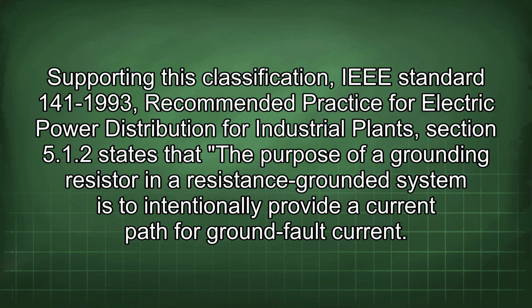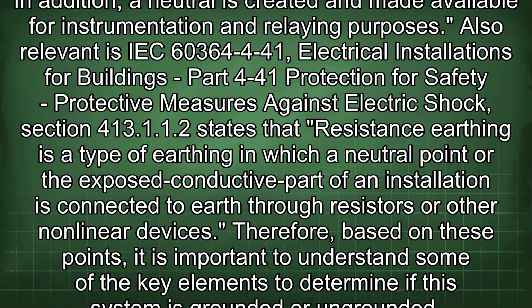Supporting this classification, IEEE Standard 141-1993, Recommended Practice for Electric Power Distribution for Industrial Plants, section 5.1.2 states that the purpose of a grounding resistor in a resistance grounded system is to intentionally provide a current path for ground fault current. In addition, a neutral is created and made available for instrumentation and relaying purposes. Also relevant is IEC 60364-4-41, Electrical installations for buildings, Part 4-41: Protection for Safety, Protective Measures Against Electric Shock, Section 413.1.1.2, which states that resistance earthing is a type of earthing in which a neutral point or the exposed conductive part of an installation is connected to earth through resistors or other nonlinear devices.